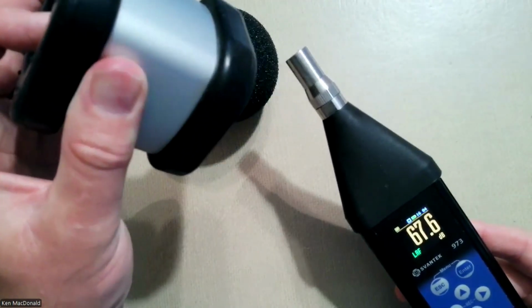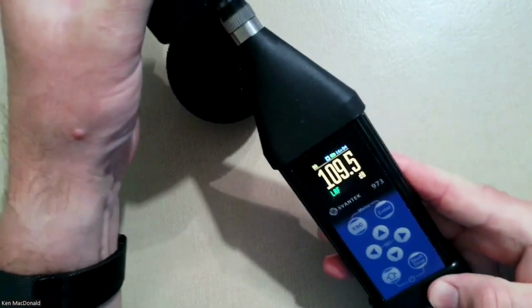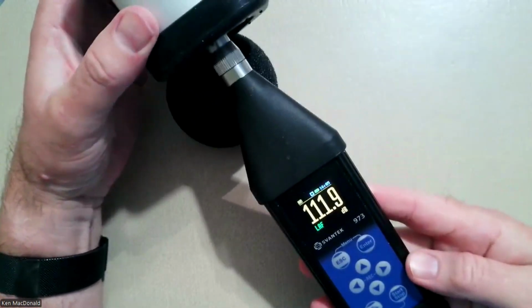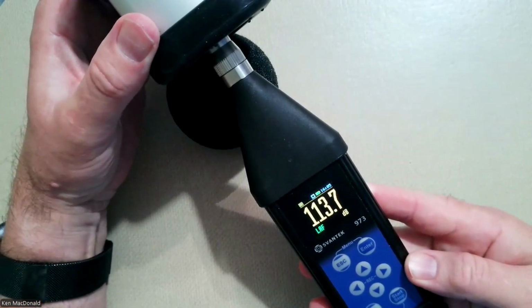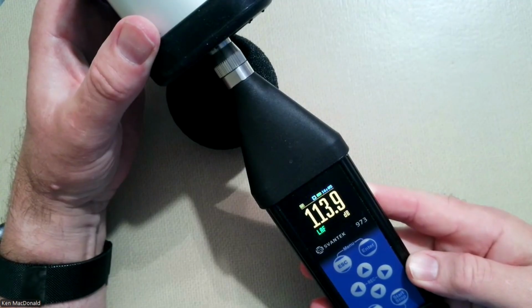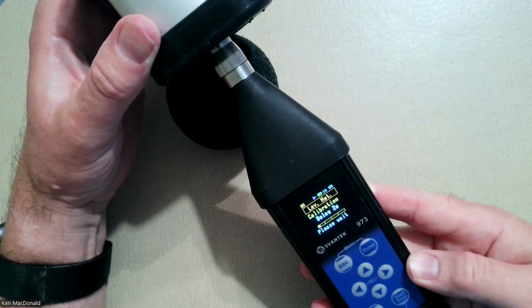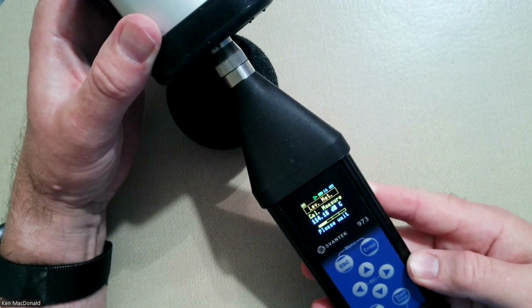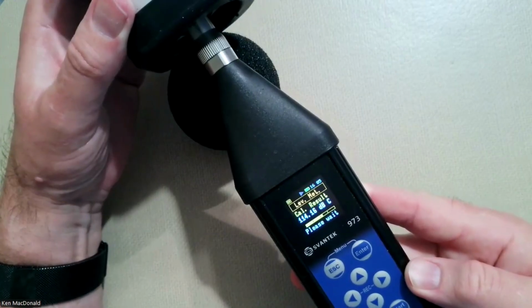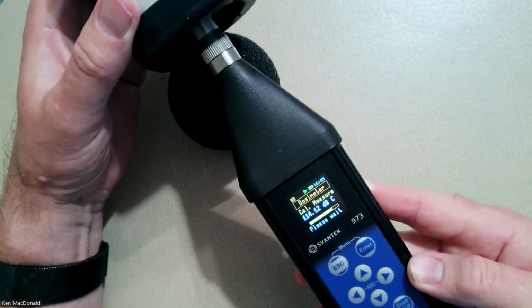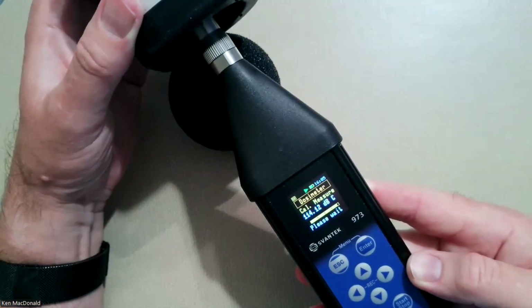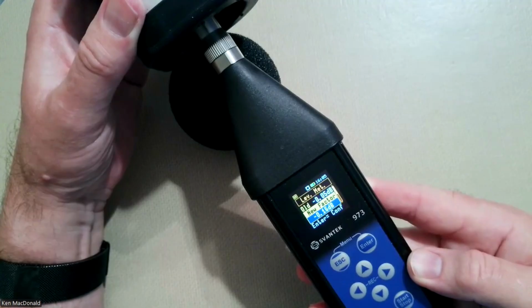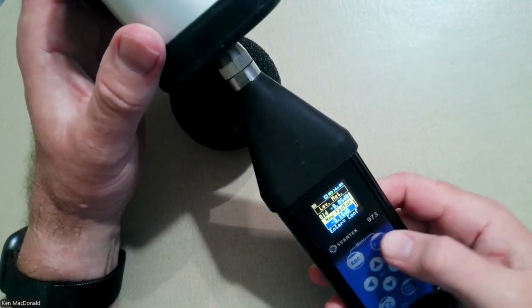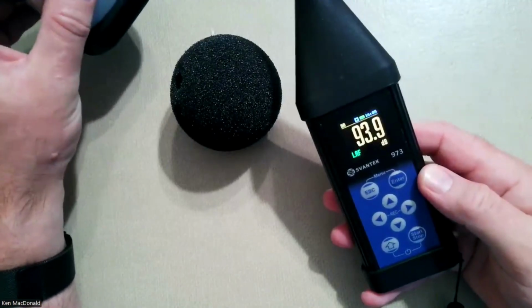But that's in a separate video. So I've got the windscreen removed. I'm going to click on the calibrator. I'll put it over the end of the sound meter. And we let it sit there. And you can see that it's getting close to 114. This is a 114 decibel calibrator. Okay, so it's picked up the calibrator's attached. It's starting the calibration. It should finish in a second. And it shows the new factor, and I can press enter to accept that. And I'm ready to use the meter now.